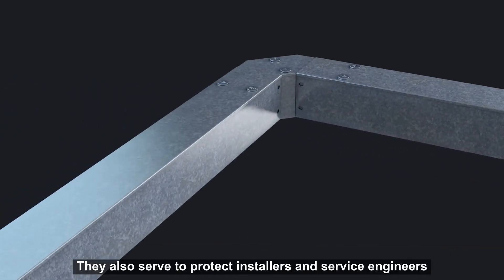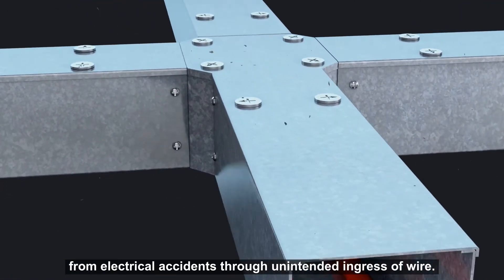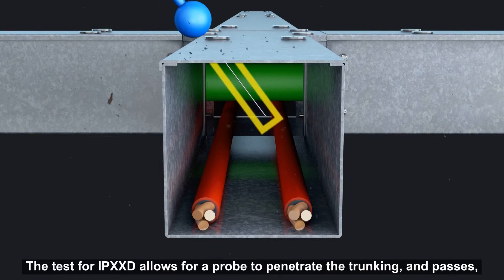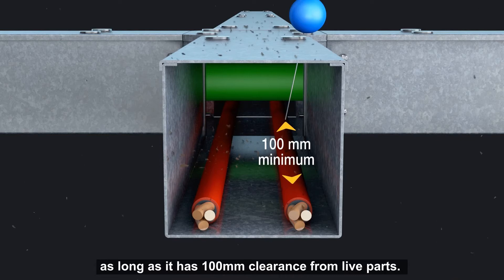They also serve to protect installers and service engineers from electrical accidents through unintended ingress of wire. The test for IPXXD allows for a probe to penetrate the trunking and passes as long as it has 100mm clearance from live parts.